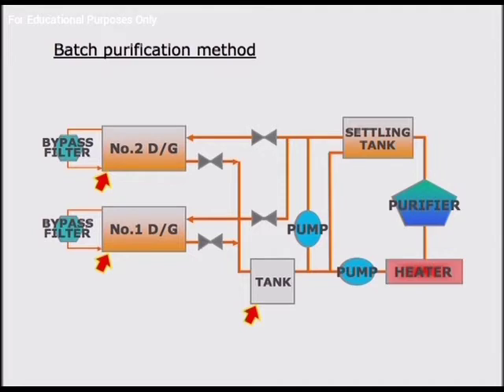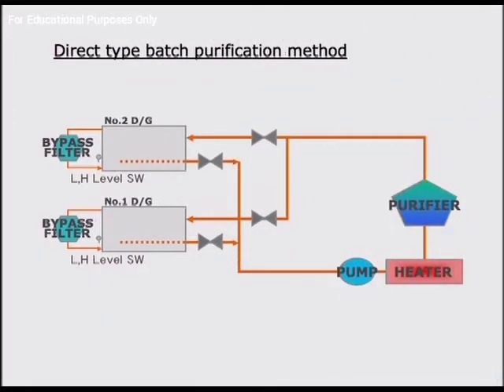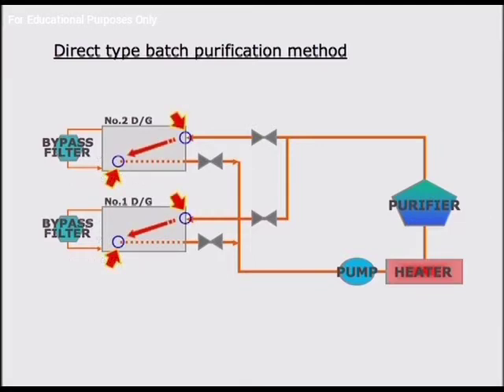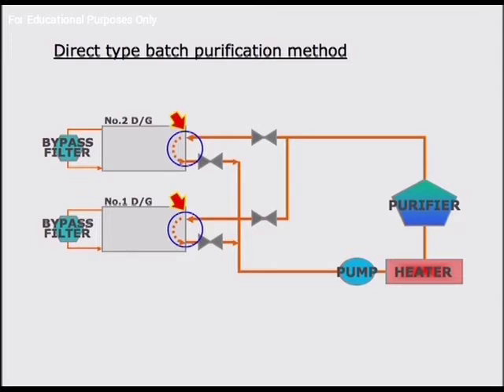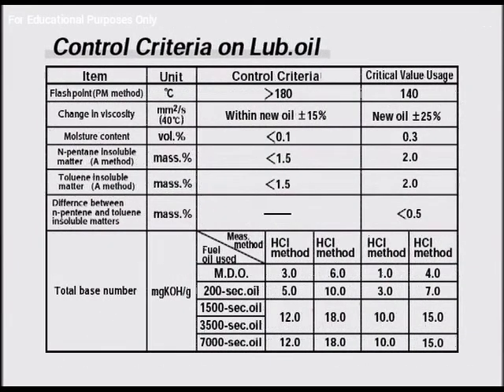Regularly carry out the cleaning of both the sump tank and overflow tank. In the case where there is no settling tank, conduct the cleaning treatment by connecting the sump tank with the purifier one-on-one. Make sure that the takeoff position of the lube oil is distant from the return position, as you cannot obtain the cleaning effect if the takeoff and return positions are too close together.